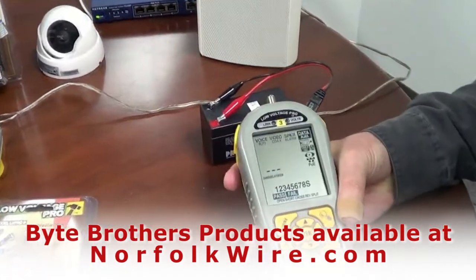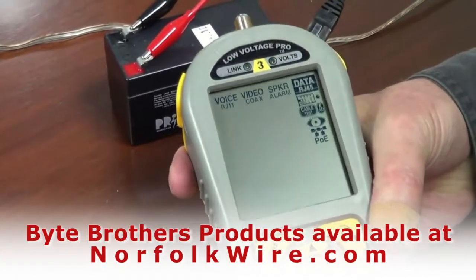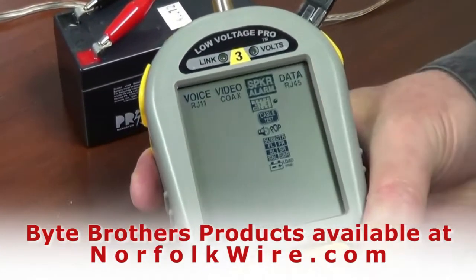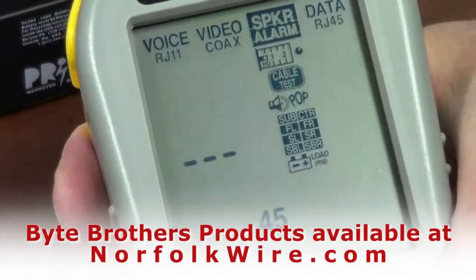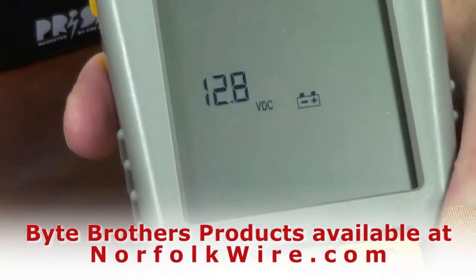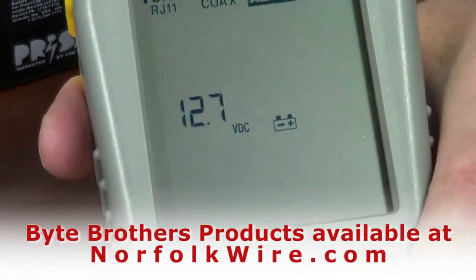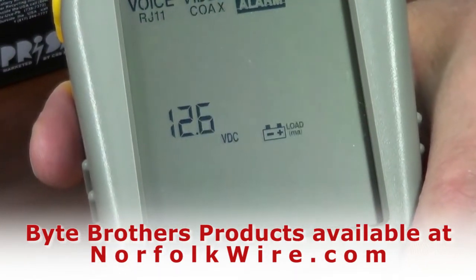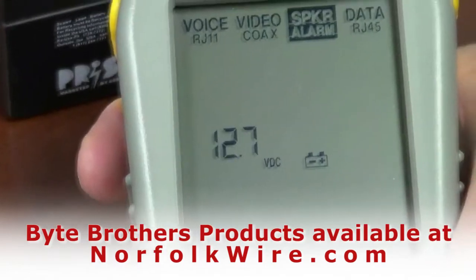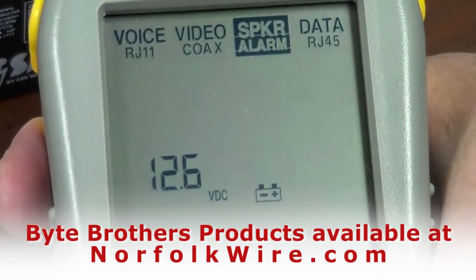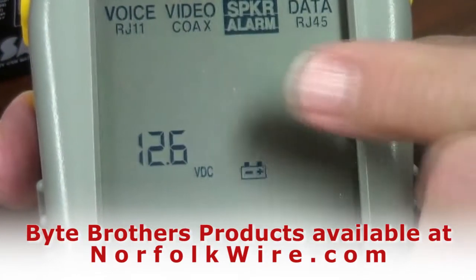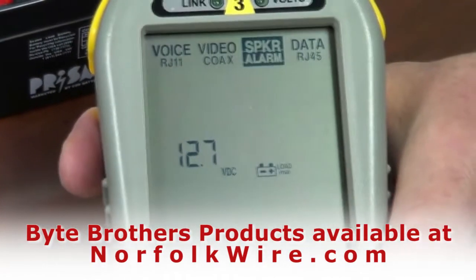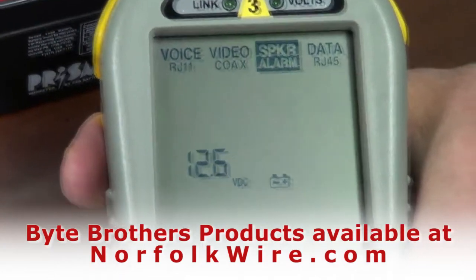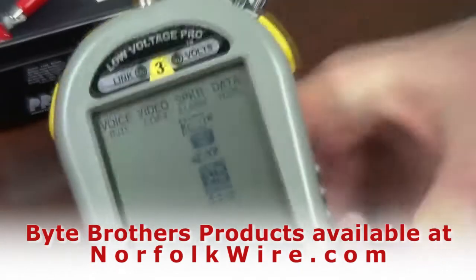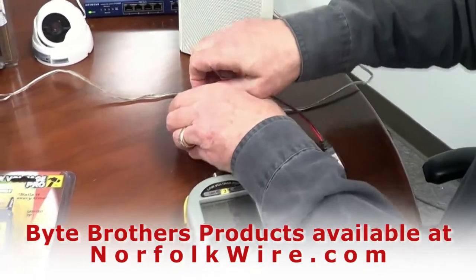I'm going to go to speaker alarm, and go all the way down to the bottom to battery test. I'll press OK to start the test. Every time I press OK, I put a load on the battery, a 100 milliamp load, and we're looking to see if the voltage of the battery drops significantly. It says 12.6 volts, but notice it doesn't drop significantly, so that's good - we've got a good battery. I'm going to exit out of the battery test.